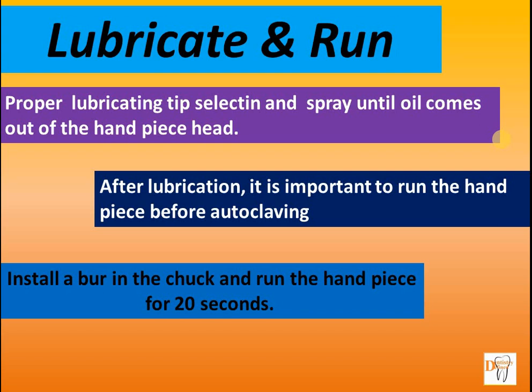Install a bur in the chuck and run the handpiece for 20 seconds. After lubrication, it is important to run the handpiece to evenly distribute oil through the bearings and to expel excess oil to prevent coagulation during autoclaving.